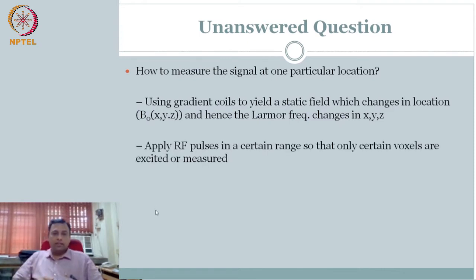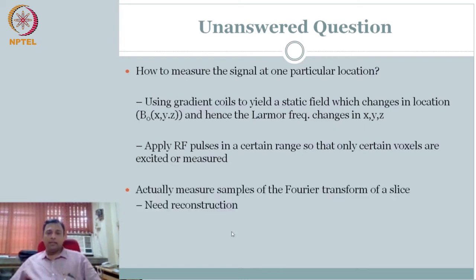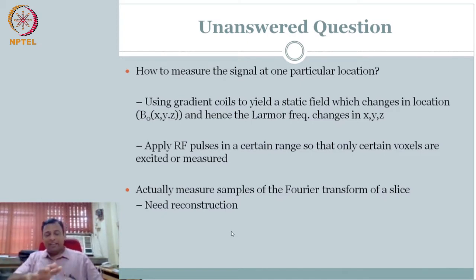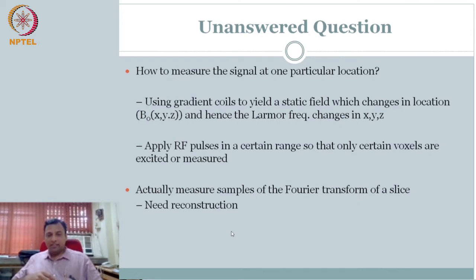Then we will talk about applying the magnetic field and manipulating it. You have to have RF pulses that you can apply when you want. Finally, you measure the signal. The challenge in MRI is that we are always measuring the signal in the time domain, which is complicated — and then doing all the signal processing. The beauty and also the challenge is that the data you are actually measuring is the sampling of the frequency spectra.